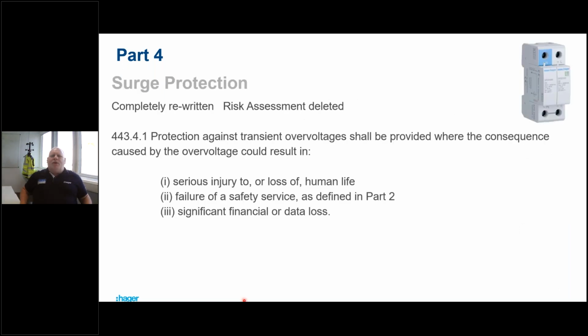The next thing we jump into is surge protection. This is another big area that's changed for us. They've completely rewritten the surge protection regulation. The risk assessment that we used to have to do has been totally deleted, so we've got rid of that risk assessment. So the regulation now says protection against transient overvoltages shall be provided where the consequence caused by the overvoltage could result in... Now they've changed this.